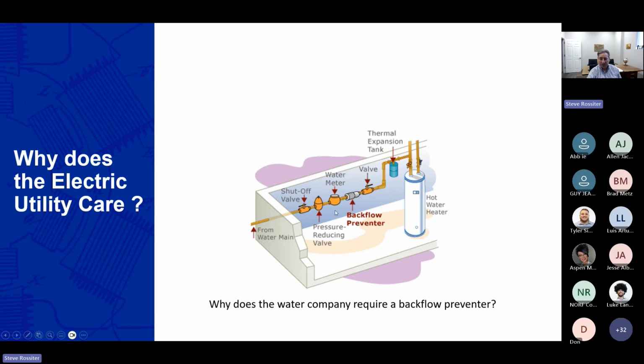It's similar, analogous to pressure. We've got the flow, which is analogous to the amps. And we've got valves, which would be just like these cut-off devices. But the backflow preventer is not really available in the electrical system. It really consists of how we mitigate harmonics, either at the source, or how we cancel those out or trap them or do something about them so they don't go upstream into the utility grid, which could affect other customers. So that analogy of a backflow preventer, I think, is a great one.